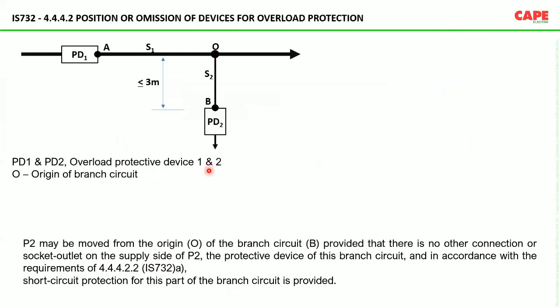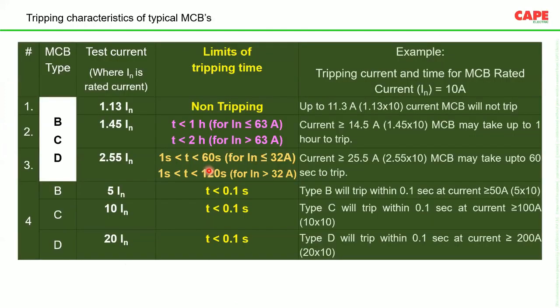Similarly, positioning of the device is very important. For example, I just put the tripping curves of B, C, D MCB. For all three types, B, C, or D, up to 1.13 times the nominal current, the device is not supposed to trip, no tripping. Similarly, 1.45 times IN, the disconnection time, this is called the conventional disconnection current.